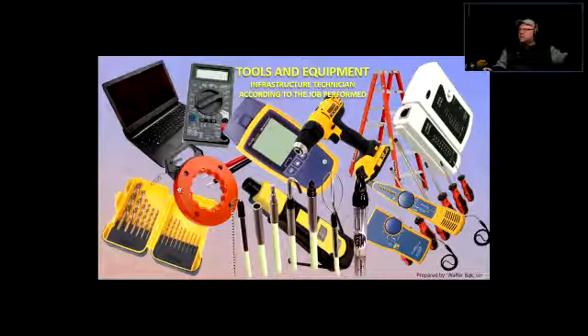What do we use that for? If it's a half inch conduit or three quarter inch conduit, 1 inch conduit, you can put in that fish tape and it's going to come out on the other side, wherever the other end is. And we grab the other end as you unroll that from this roll. And then you can attach a wire or cable to it and you can pull it back with the cable.